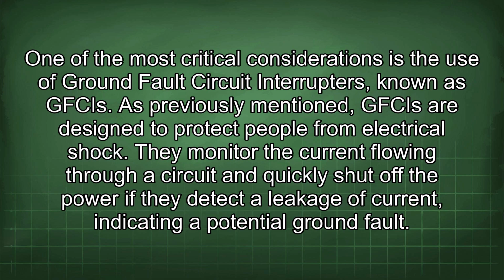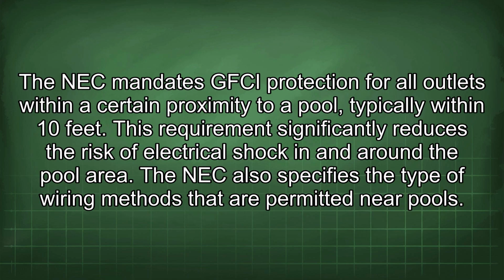As previously mentioned, GFCIs are designed to protect people from electrical shock. They monitor the current flowing through a circuit and quickly shut off the power if they detect a leakage of current, indicating a potential ground fault. The NEC mandates GFCI protection for all outlets within a certain proximity to a pool, typically within 10 feet. This requirement significantly reduces the risk of electrical shock in and around the pool area.